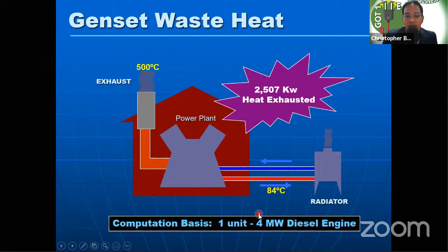Ang computation basis namin during the study is 1 unit 4 megawatt diesel engine. Yun yung basis. So what we have done is we have selected a chiller, an absorption chiller, which I will explain later. We installed a water heat exchanger na nadadaan yung heat papunta sa radiator before going to the cooling tower, and we have recovered 651 kilowatt of power. Then sa exhaust naman, naglagay din kami ng exhaust heat recovery boiler where we have recovered 1,900 kilowatt of energy. So with this, makakapag-generate yung heat exchanger namin ng around 83.7 degrees C of hot water.